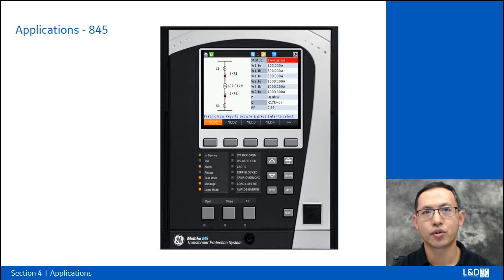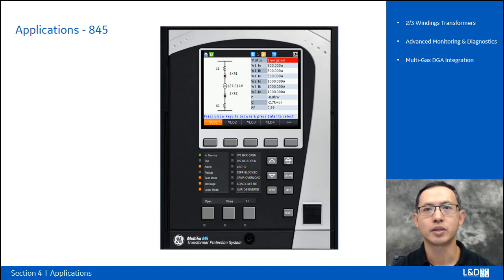issues. 845 has been designed for protection, control, and management of 2- and 3-winding power and distribution transformers in both utility and industrial applications. 845 provides advanced functions for a wide range of transformer applications, delivering high-speed protection, advanced transformer monitoring, diagnostics, and reporting with integrated connectivity to single and multi-gas transformer DGA devices for advanced warning of potential issues before they become critical transformer faults or failures. 845 enables a proactive maintenance approach, mitigating the risk and cost associated with equipment failures or replacement.